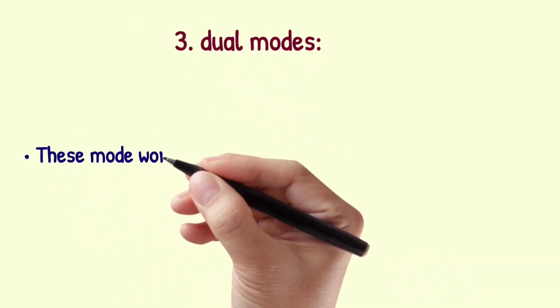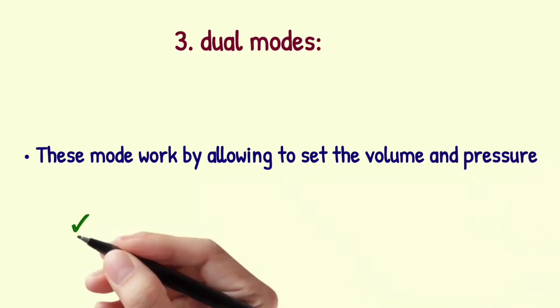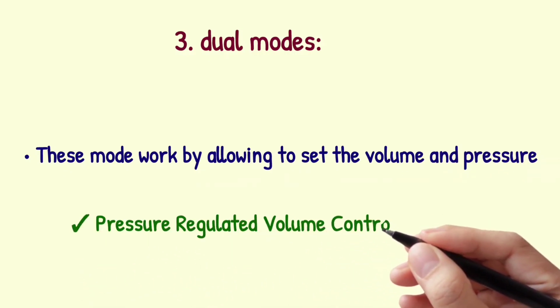This mode works by allowing you to set the volume and pressure. Pressure regulated volume control is a dual mode.